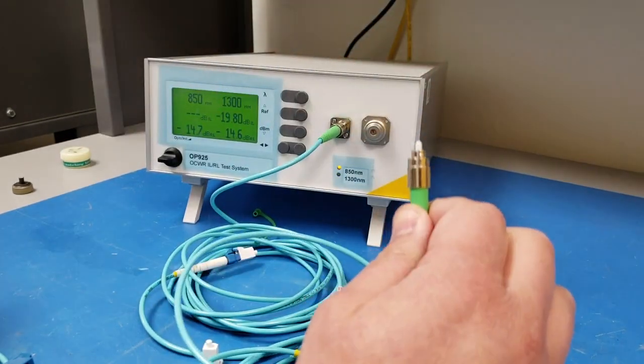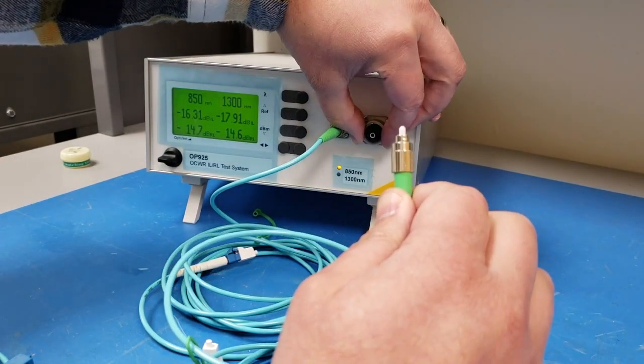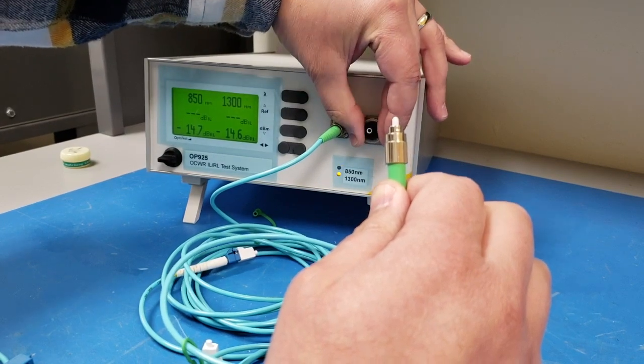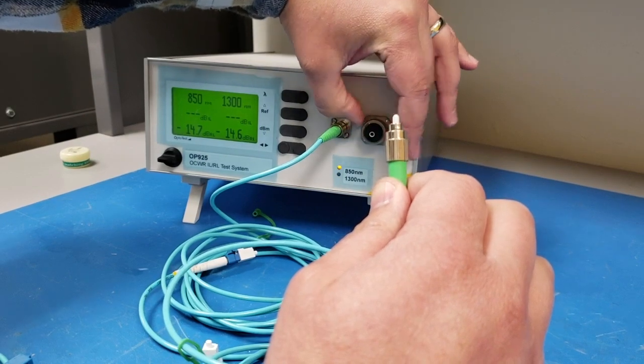So because I have an unlike connector here which is an APC 2.5 millimeter ferrule, I need to change out the adapter here from the 1.25 to the 2.5 millimeter ferrule adapter.